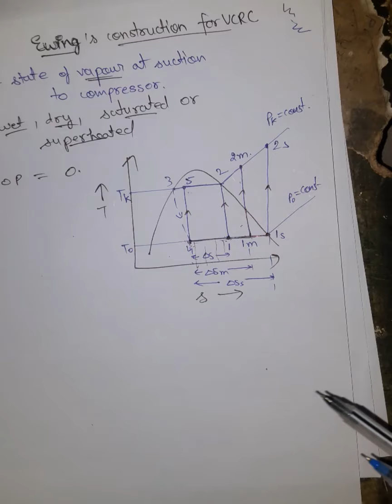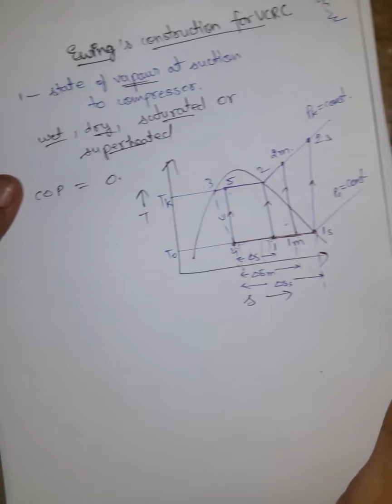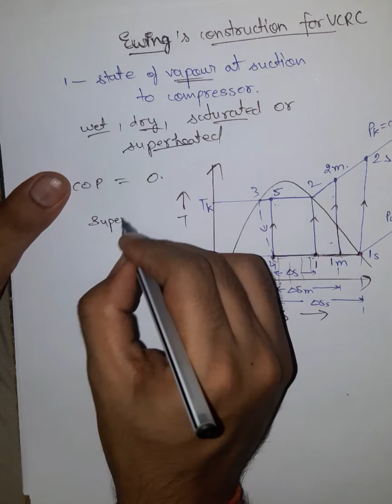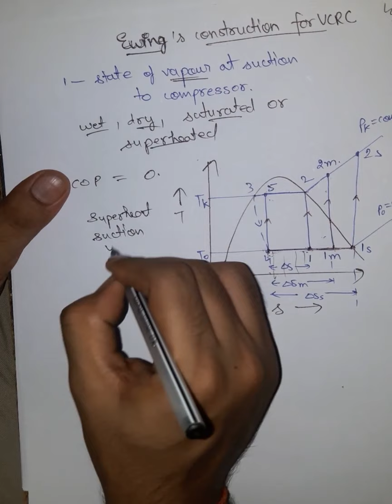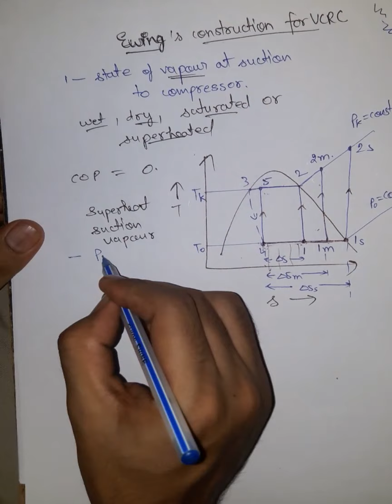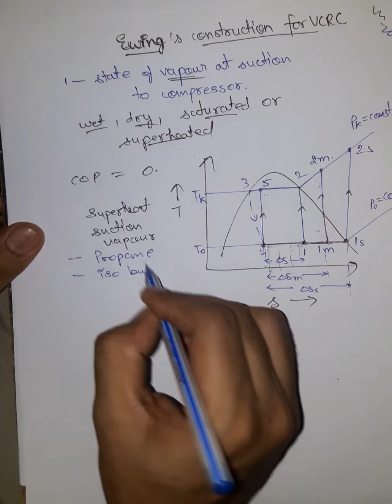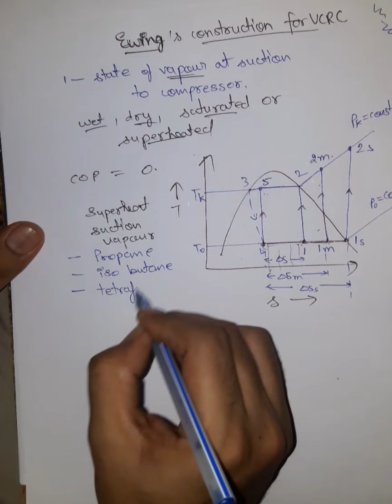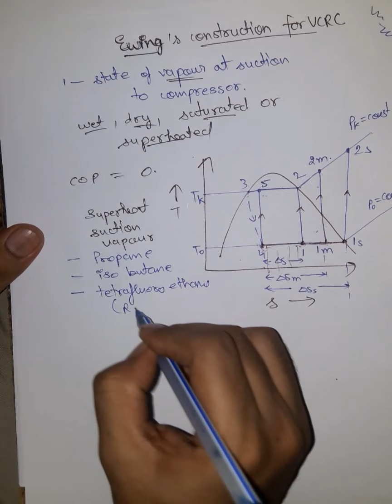He suggested which refrigerants have COP increasing in the superheated region, and for which refrigerants the wet suction state, that means suction starting in this region, gives the maximum COP. Okay, so I am writing some of the examples over here. For superheated suction vapor, the COP increases for the following refrigerants, that is propane, isobutane, and tetrafluoroethane, which is also known as R134a, and R12.